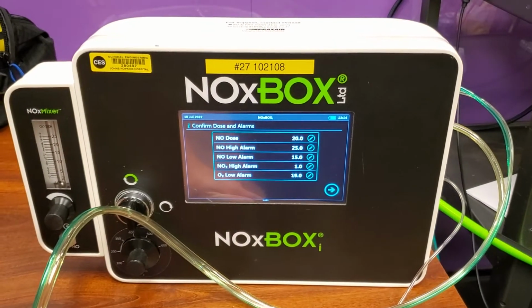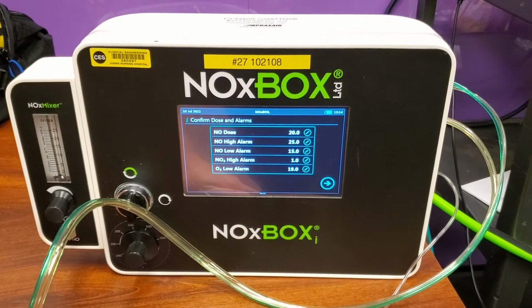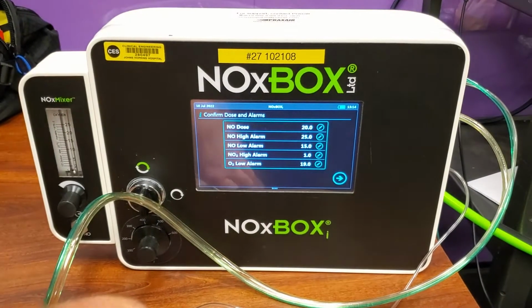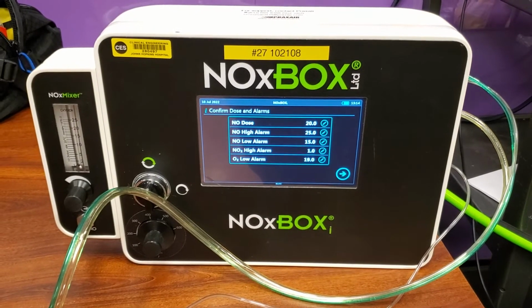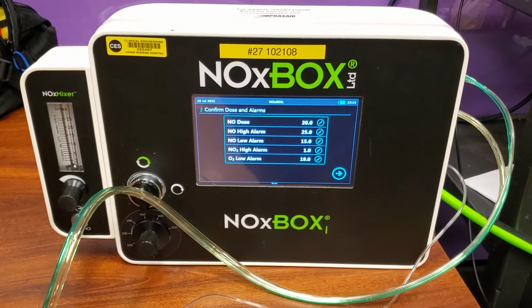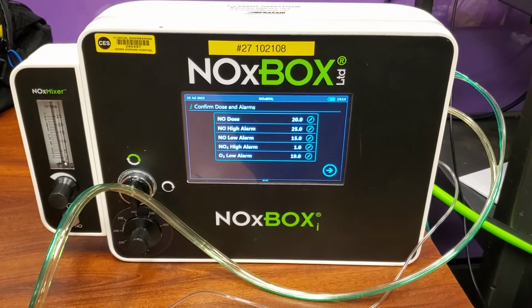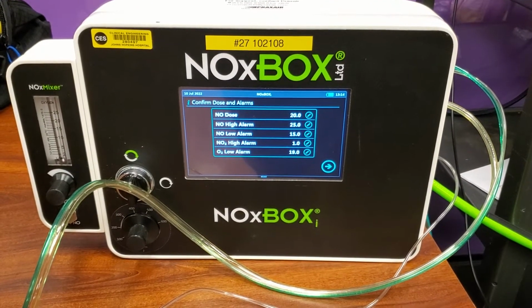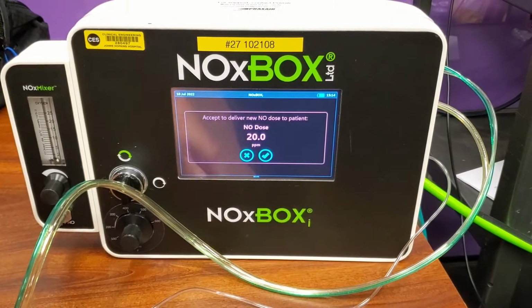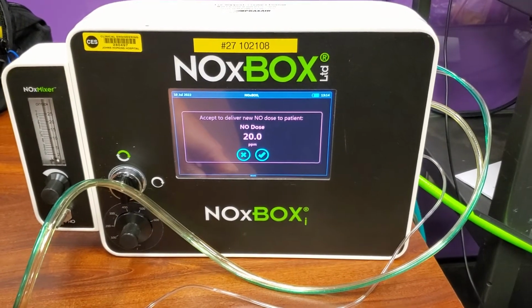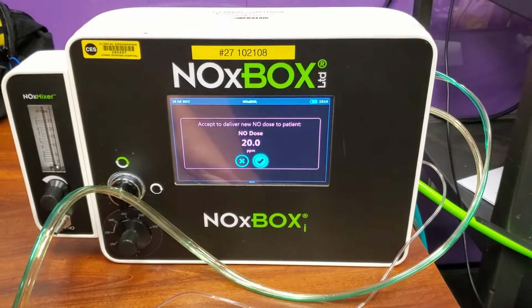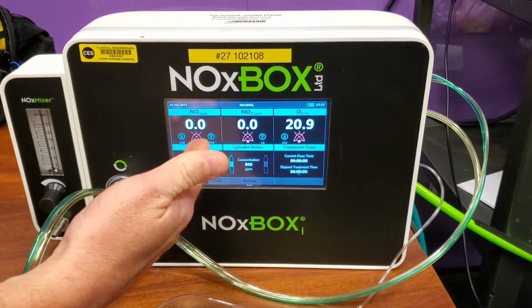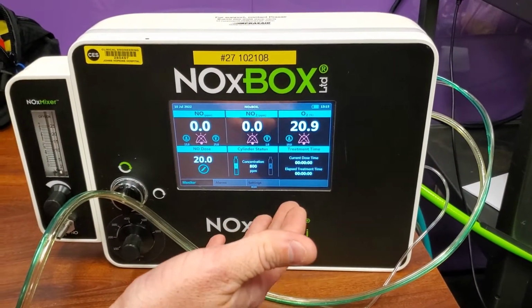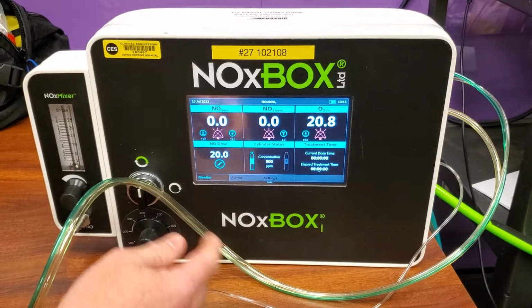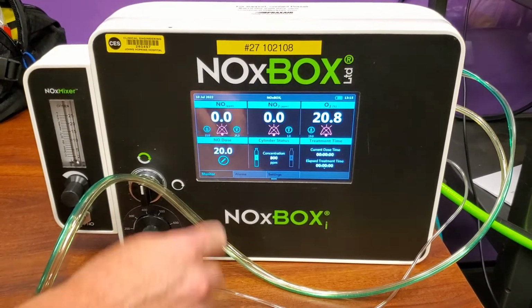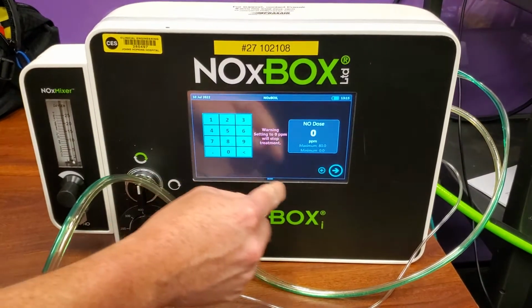I will let you know that when you do initially put it on the patient, it does take a minute or two to realize exactly the flow of the ventilator and how much nitric it needs to give. So you might see some wild swings in how much the patient's receiving at first, but it will plateau out after a couple of minutes or so. Moving on to our next page here. Now it's going to prompt us to accept to deliver the new dose. Going to click our check there. So now we are giving the patient the nitric. It's going to alarm us in a minute because we don't have anything going through the ventilator, but obviously that is how we would go about it for their dose there. So let's go ahead back here and we'll set our dose back to 0.